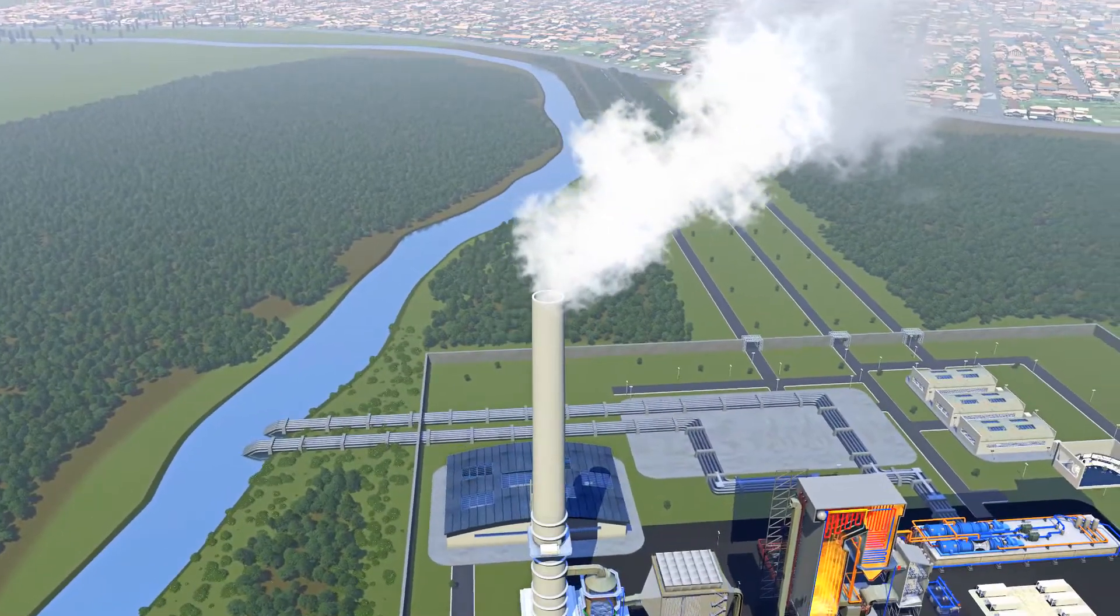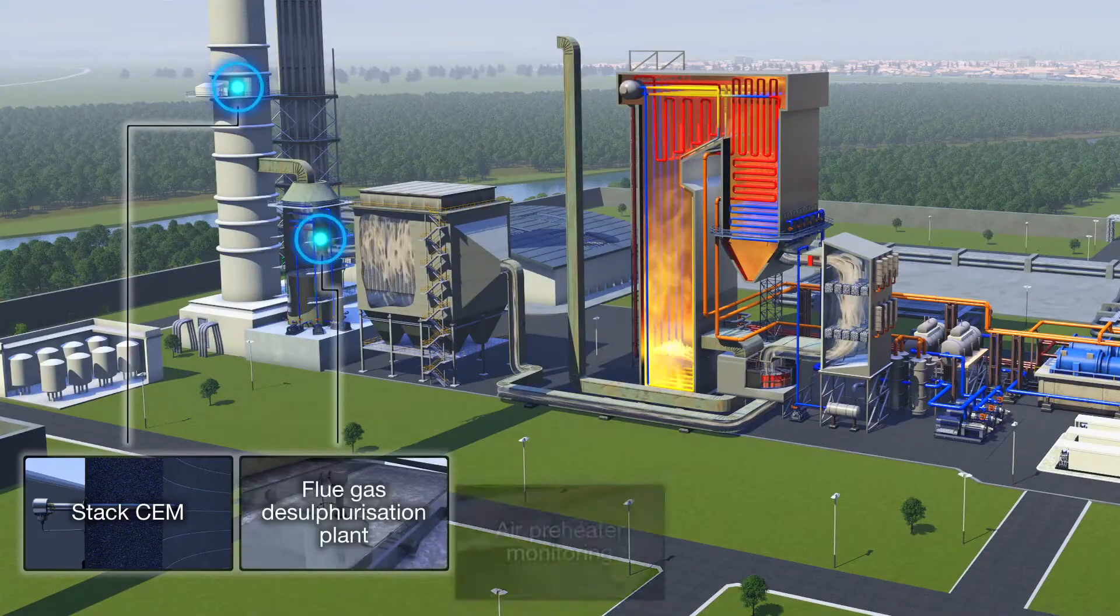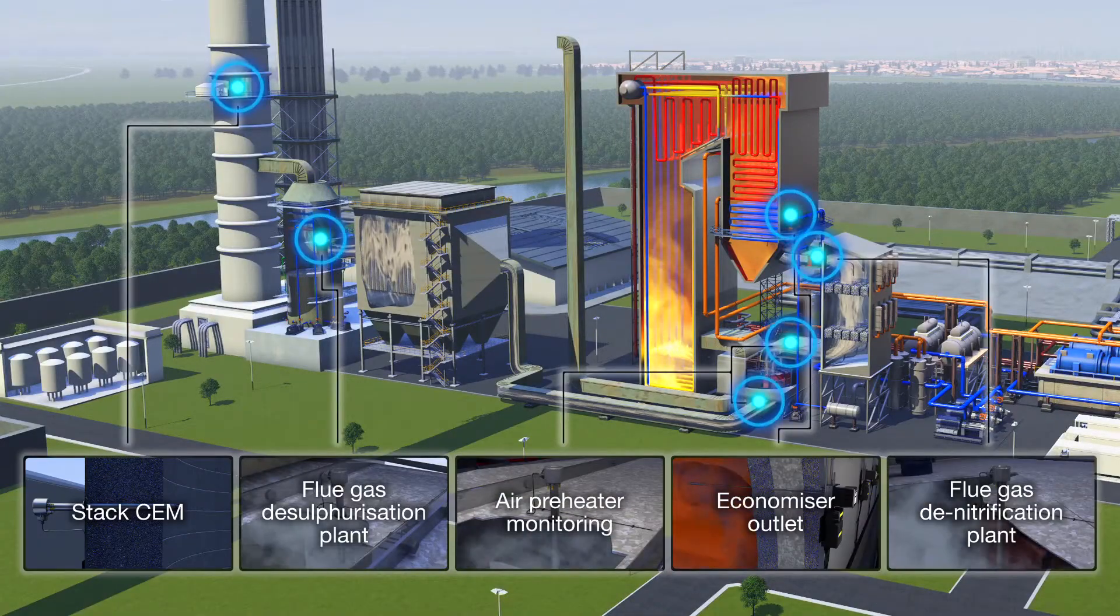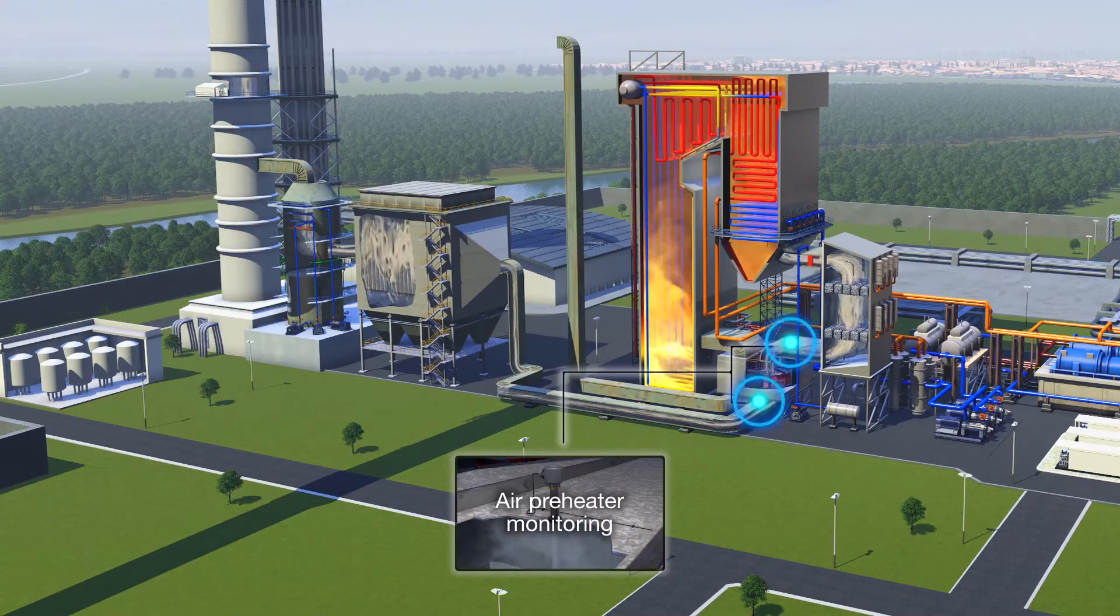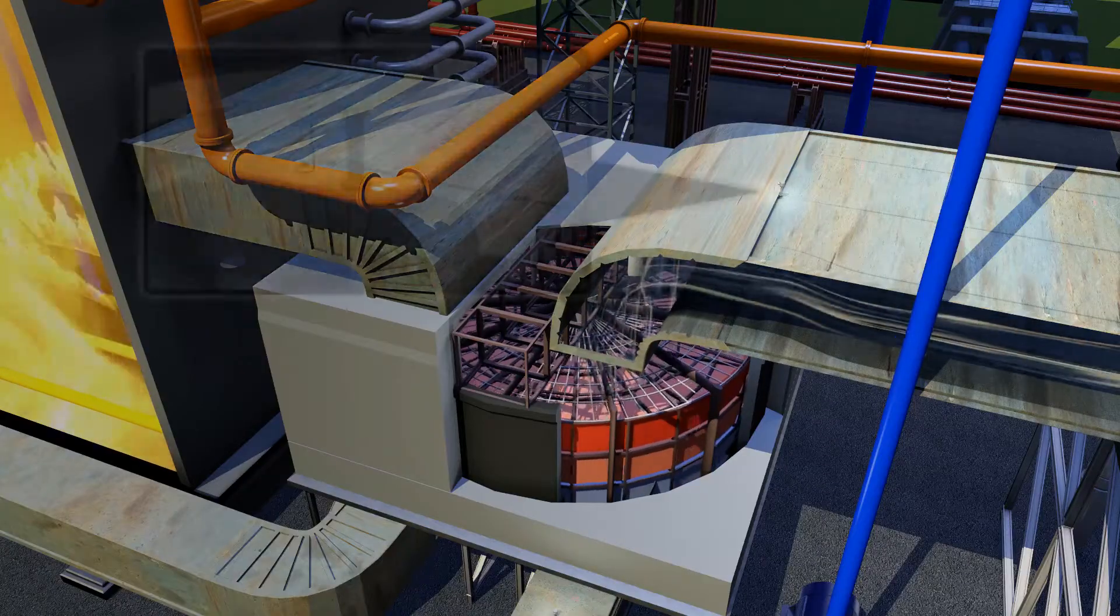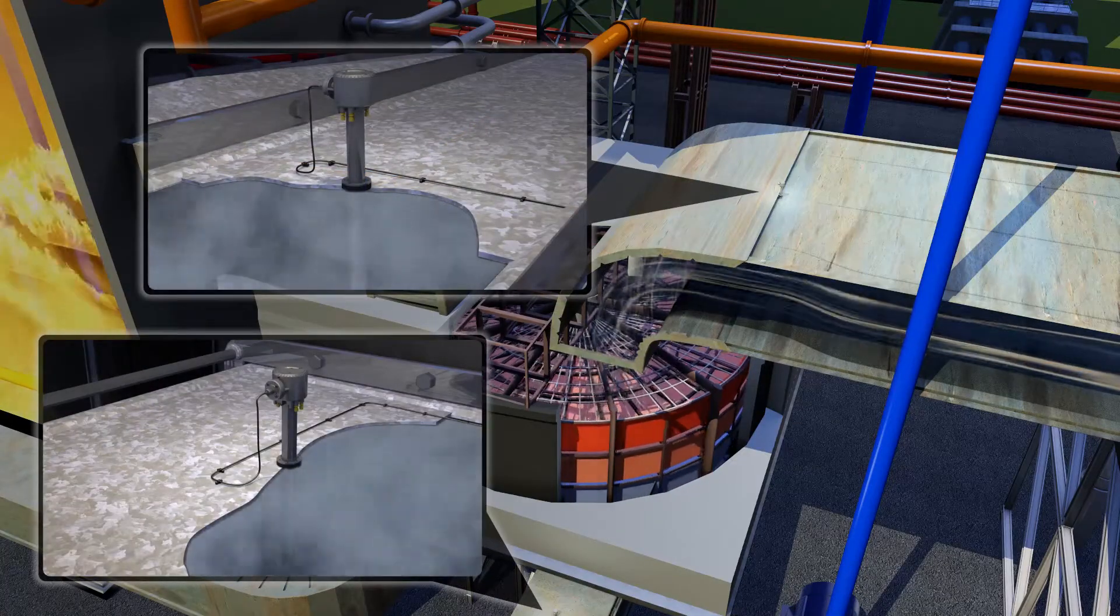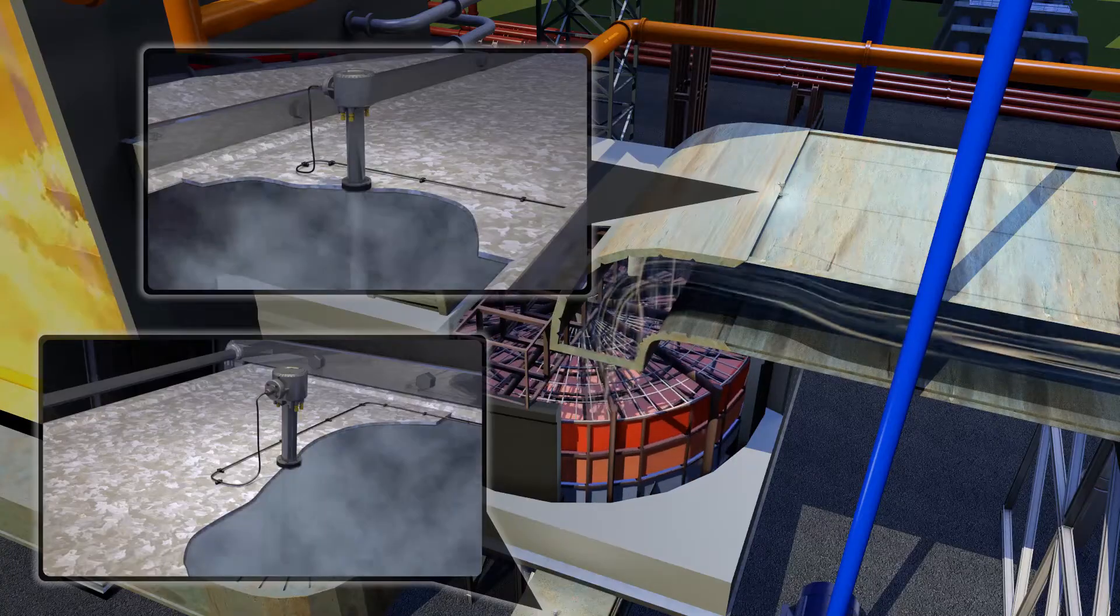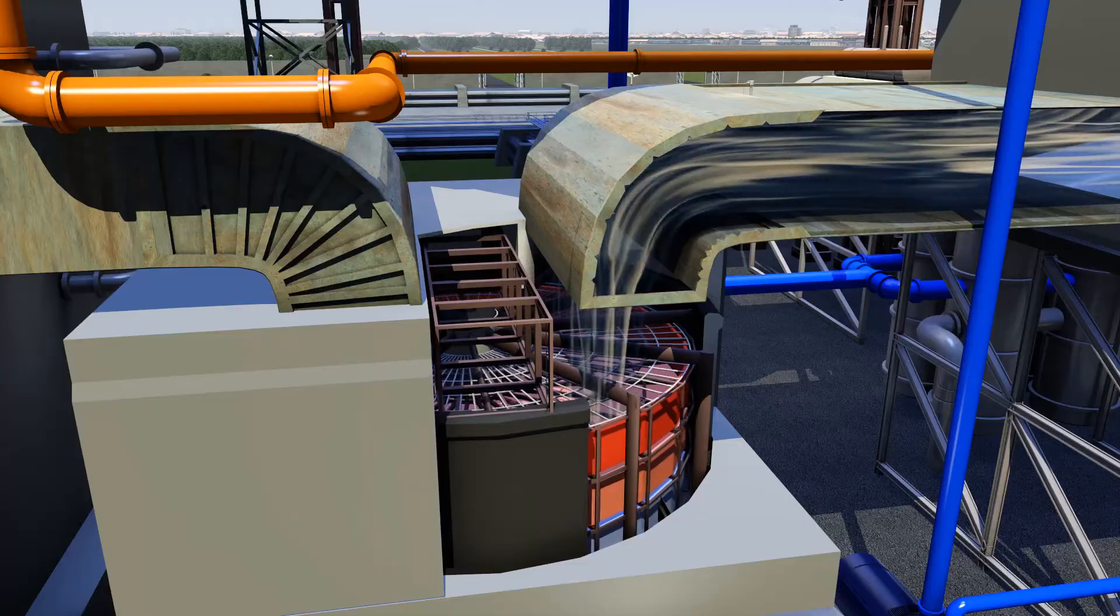ABB's AZ Analyzers can be used to measure efficiency at key points in the power generation process, including Air Preheater Monitoring. By measuring and comparing excess oxygen levels at the entrance and exit of the air heater flue gas stream, ABB's AZ-20 zirconium oxygen probes can help provide an accurate assessment of the performance and condition of air heater plant.